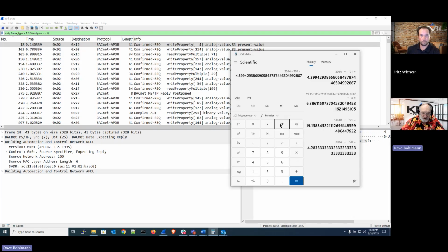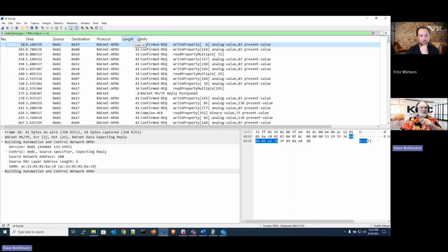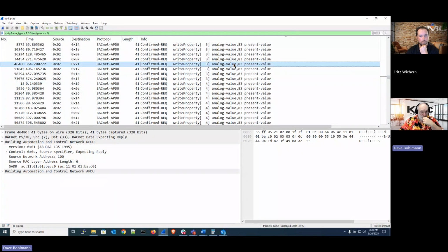And why is it doing that? I don't know, so that would be one thing you could check. Then what we could do is see who else is passing on messages. But one hint, too, about why it is sending so many: if I click on info here, I've left that, so again this is only the requests coming from the operator station, and you notice it sure is, here it's actually writing to AV83.